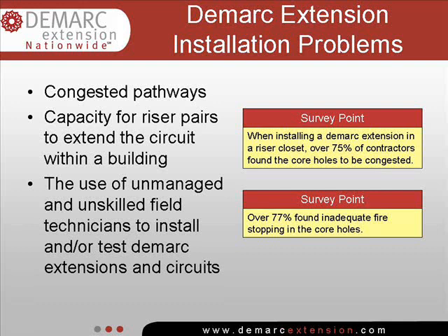Congested pathways can impact the installation of cabling, typically occurring in the core holes of stacked telecom closets. Capacity for riser pairs to extend the circuit within a building may be exhausted due to unavailable pairs, typically because the previous cross-connects have not been removed when service was concluded.